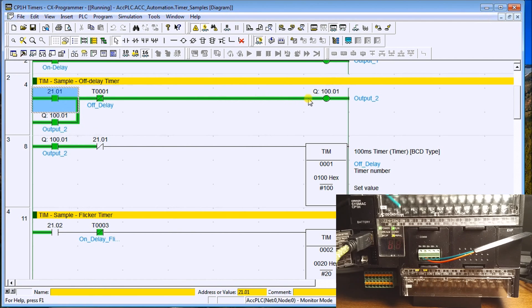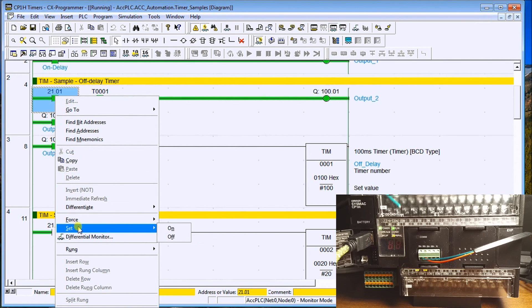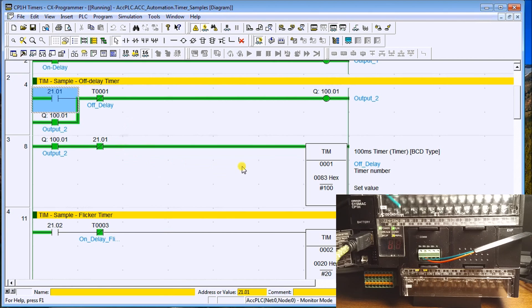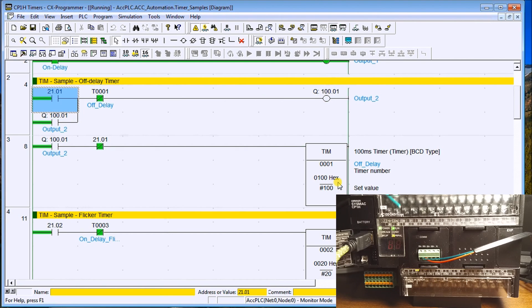When I turn the input off, the output will remain on because the input contact is now true and the timer starts timing down for 10 seconds. Once those 10 seconds expire it will open that contact, which resets the output. So when I lose the signal it delays the output off by 10 seconds. You can see the timer timing down, and once it hits zero the output turns off — that's the off-delay timer.